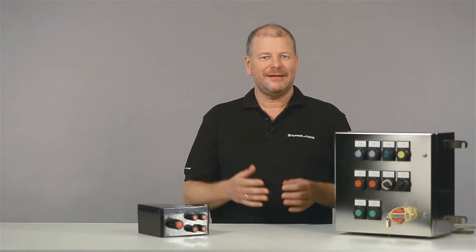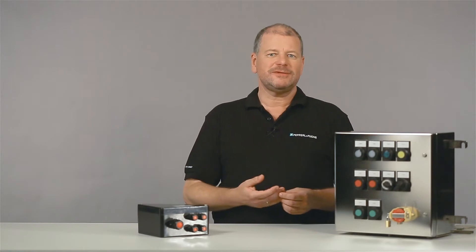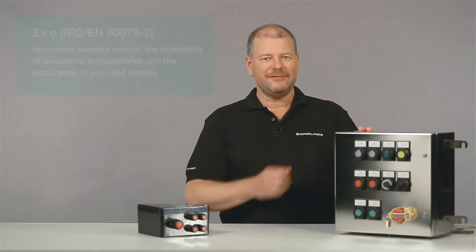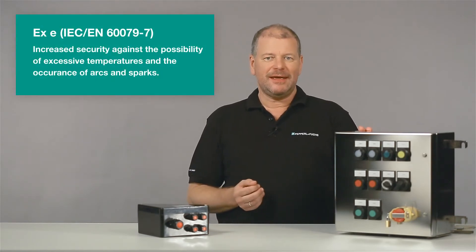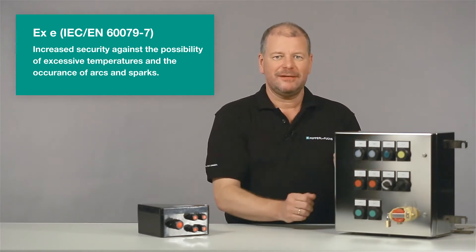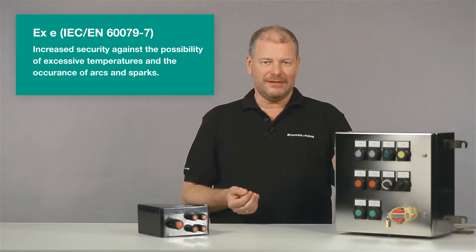Ex e is defined in the international standard IEC EN 60079 Part 7. By means of specific design features, impermissible high temperatures as well as the occurrence of sparks and arcs inside or on the outside of an electrical apparatus are avoided.